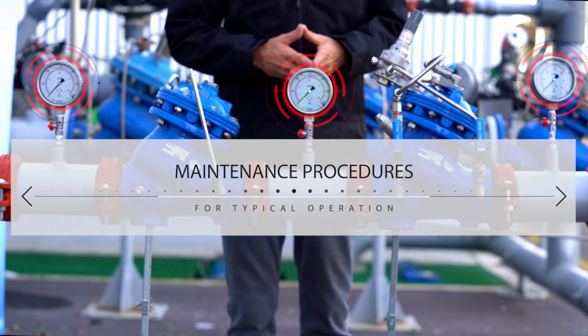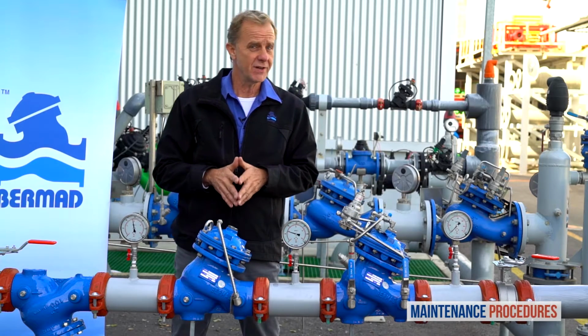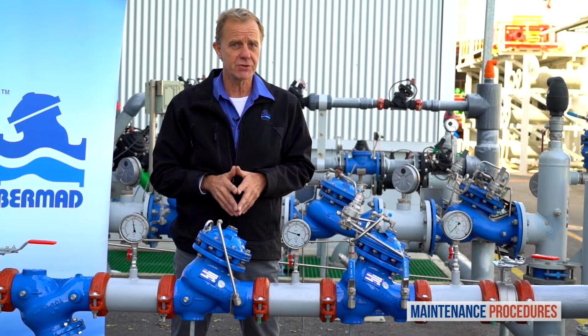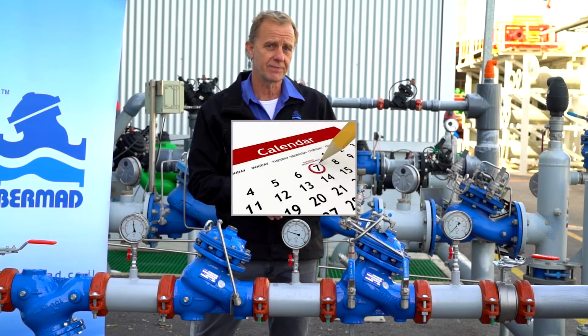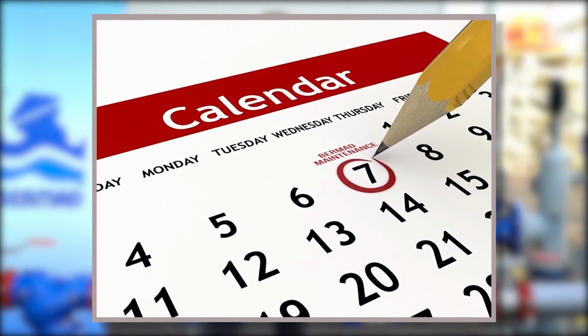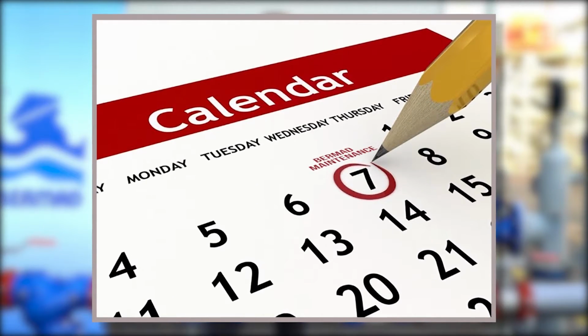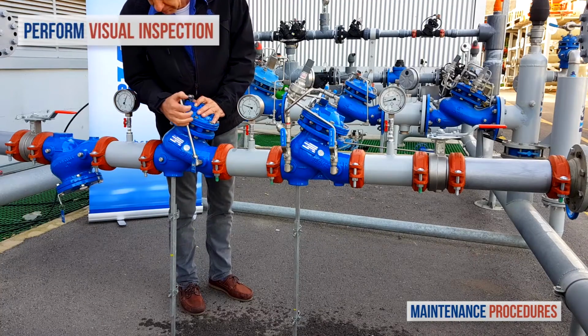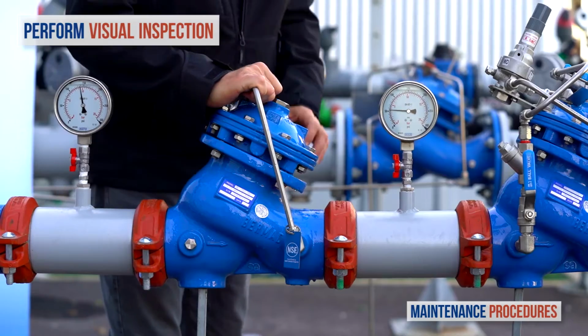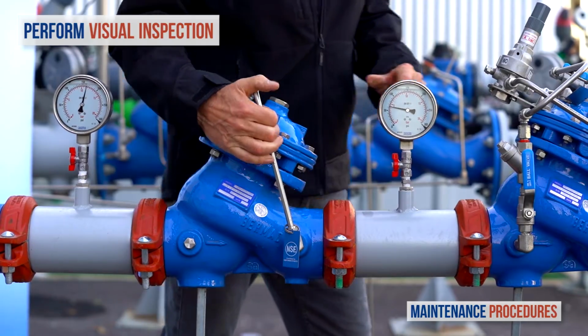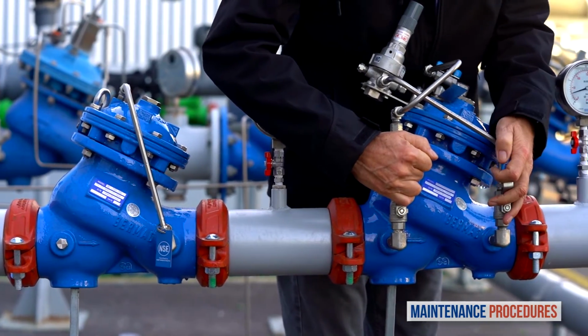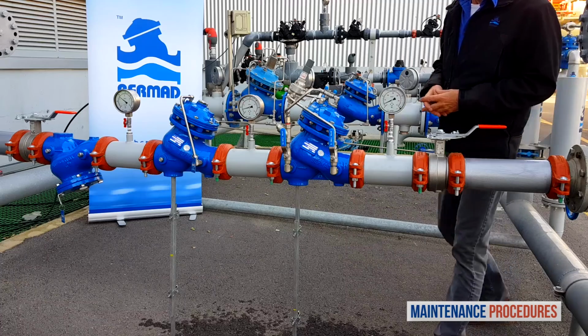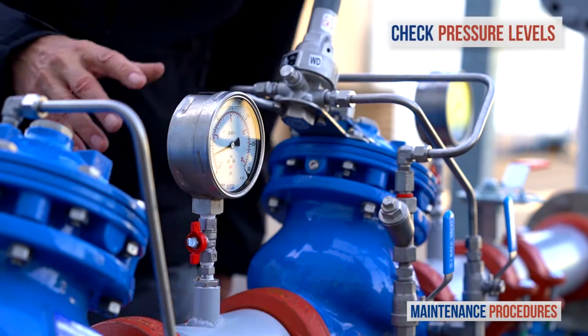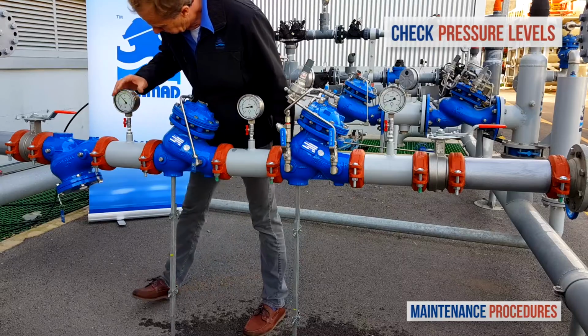Now let's discuss maintenance procedures for the Bermad PRV two-stage pressure reducing station. Note that your schedule for preventative maintenance depends on the actual conditions of use and the station's environment. Here we discuss a schedule suited for a valve operating under average conditions. On a weekly basis, perform a visual inspection of the station and check for leaks or external damage. In addition, observe the unit's pressure gauges to make sure that the pressures upstream and downstream are as they should be.